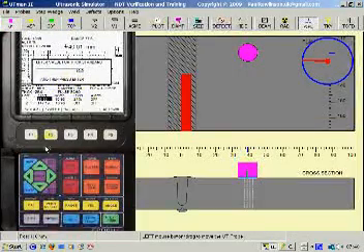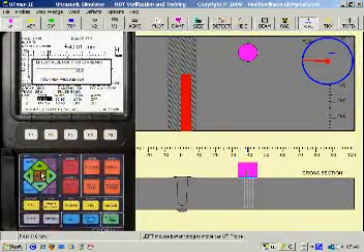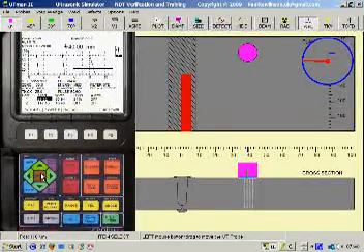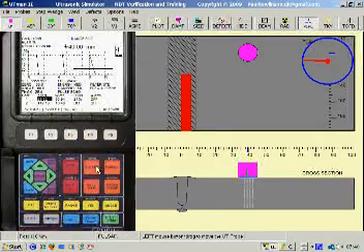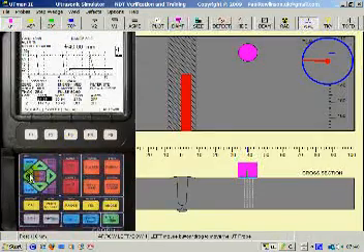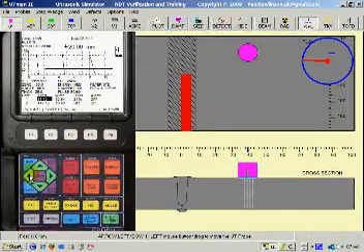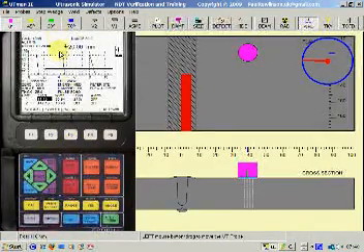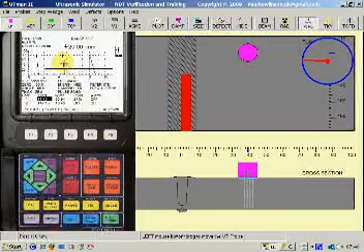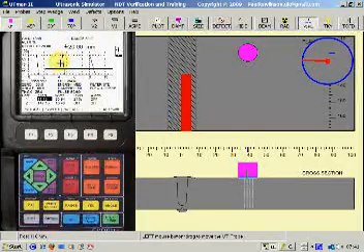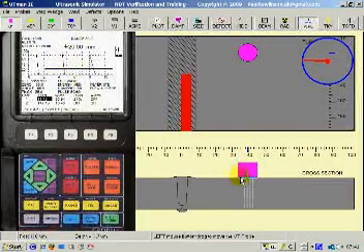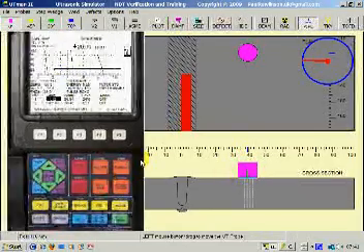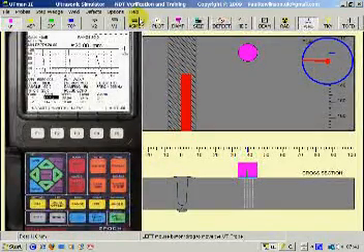And then, as it says there, press Enter. I'll put the gates back there. We've now got a perfect calibration. That first echo is reading 20, and this is a 20 millimeter thick sample.